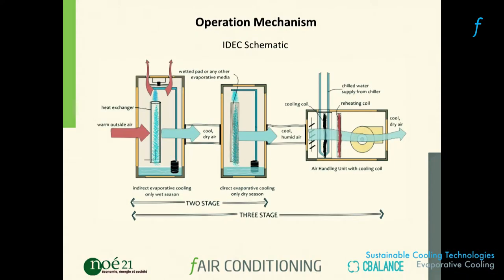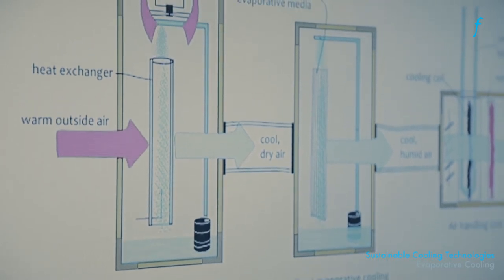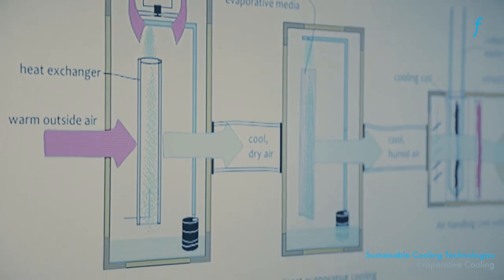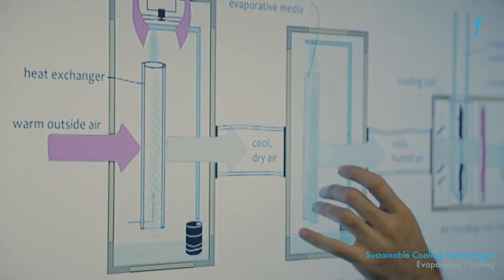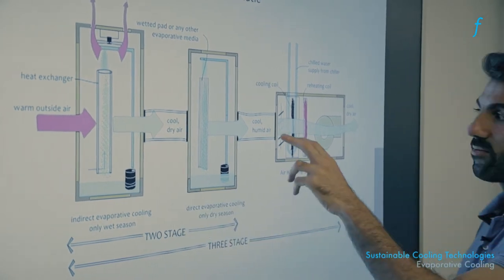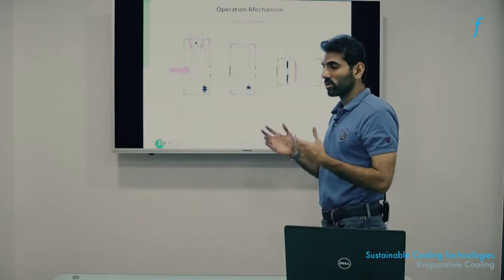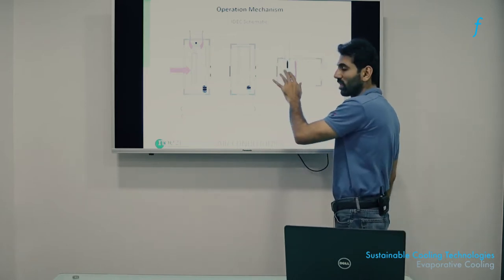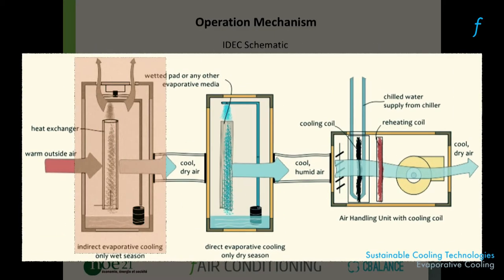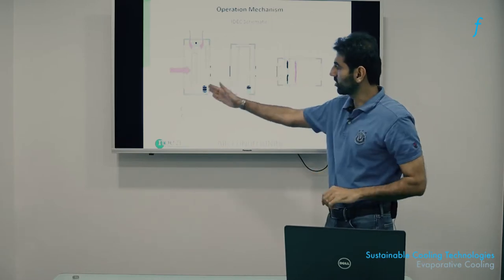A real-world IDEC system has the indirect evaporative cooling stage first, always followed by the direct evaporative cooling stage — the psychrometric chart explains why this order is used and never reversed. For very humid conditions (like Chennai, Mumbai, or Kolkata), a conventional AC unit can be added as a third stage. This creates an indirect-direct hybrid cooling system that can meet cooling needs throughout the year for any region in India. Each of these units will be understood separately.